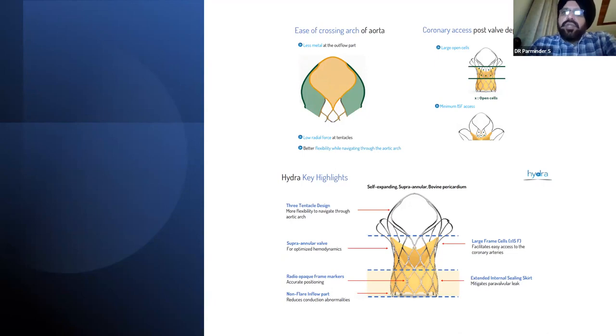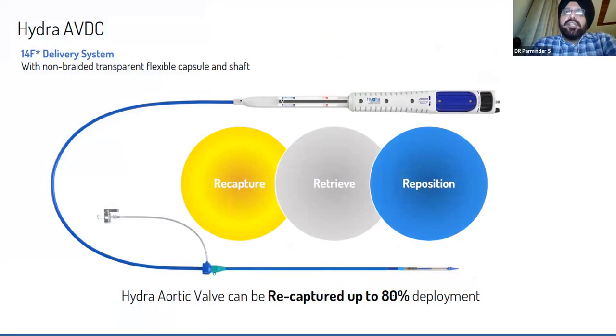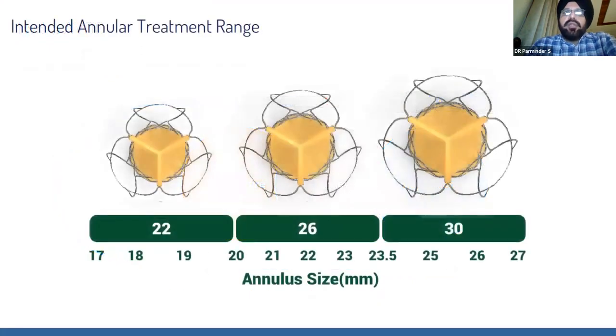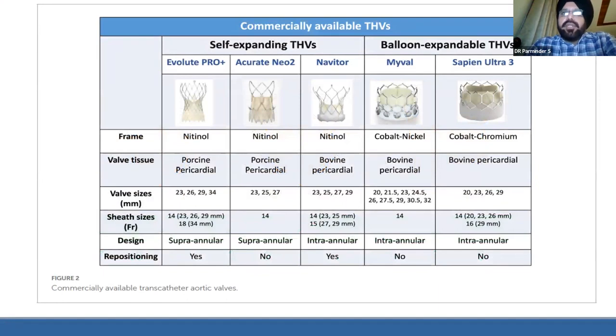It means even if it goes into the LVOT, and the LVOT is relatively larger, it doesn't cause conduction disturbances, or is potentially likely to cause fewer conduction disturbances in comparison to the CoreValve, which is, you can say, flared at the lower end. Large frame cells provide easy access to the coronaries, and there is a sealing skirt which mitigates paravalvular regurgitation. This valve is recapturable, retrievable, and repositionable up to 80% deployment, and is 14 French compatible, available in 3 sizes, and covers an annulus from 17 to 27. So these are the 5 valves which are available.